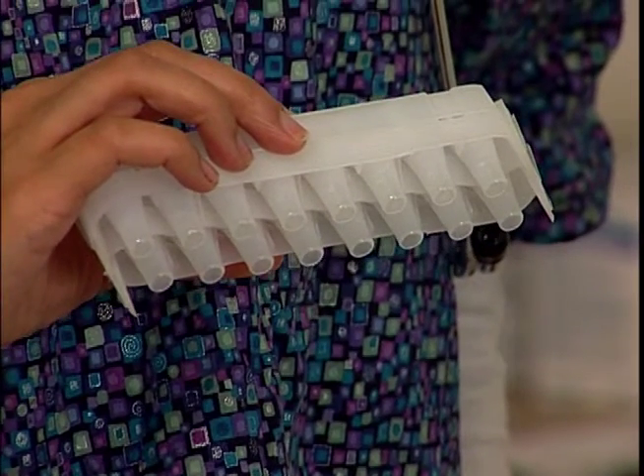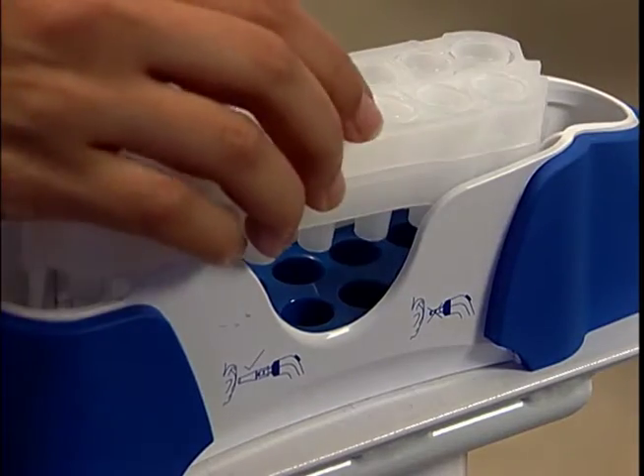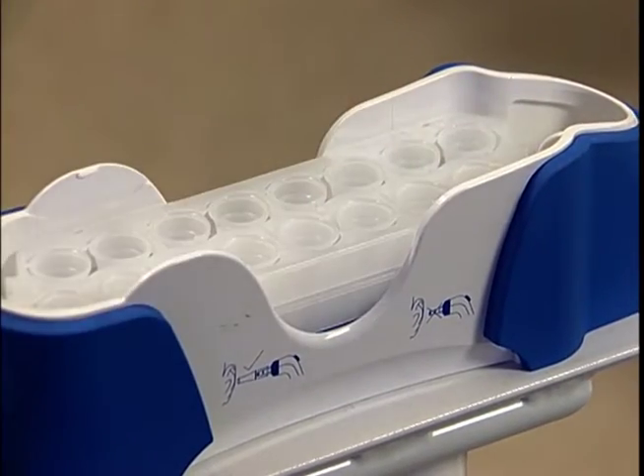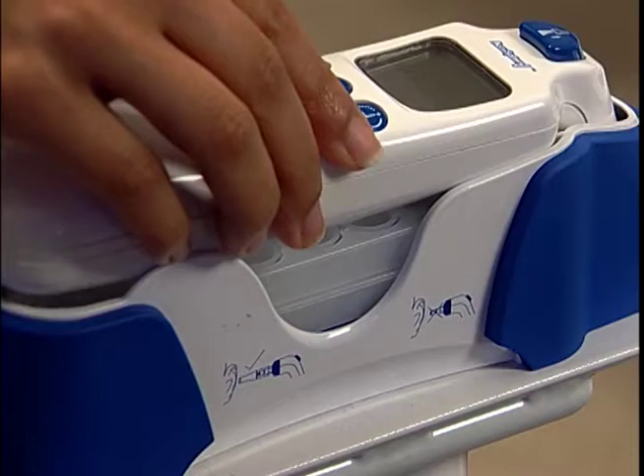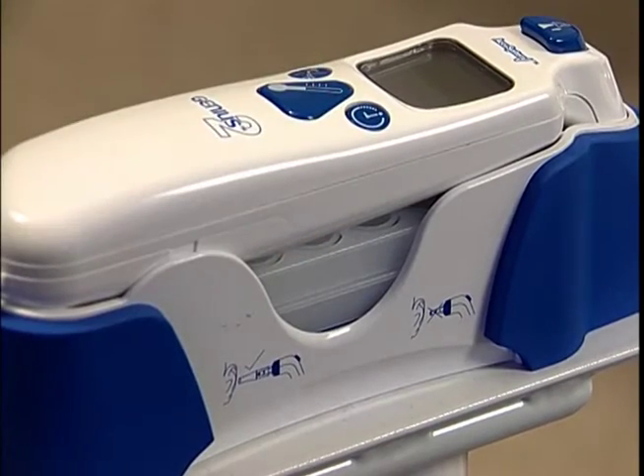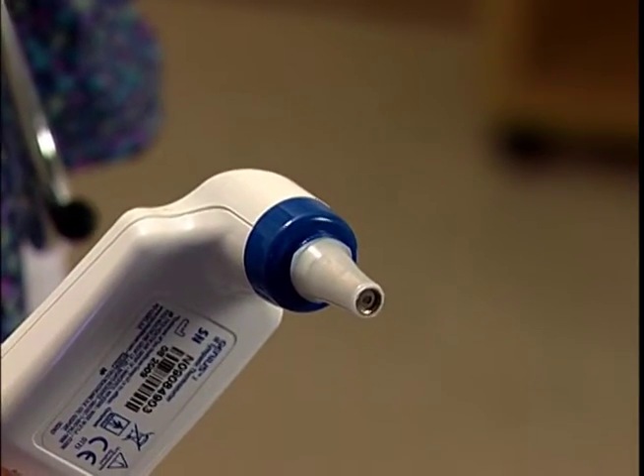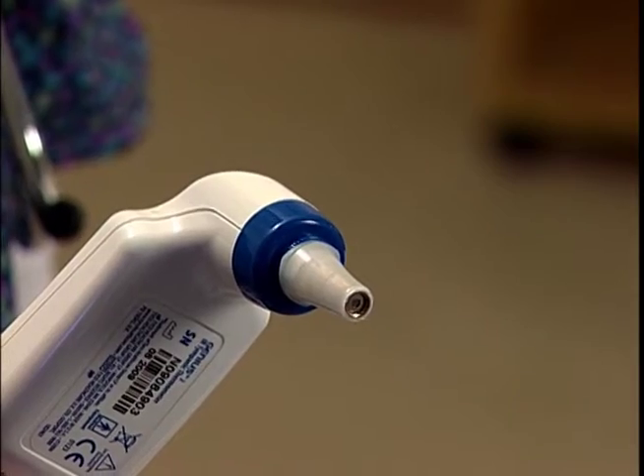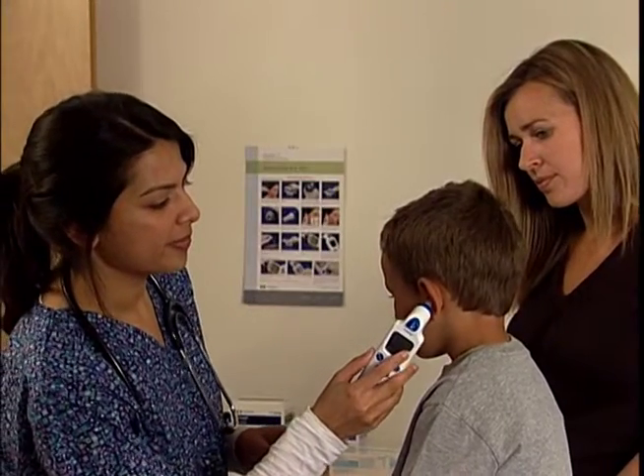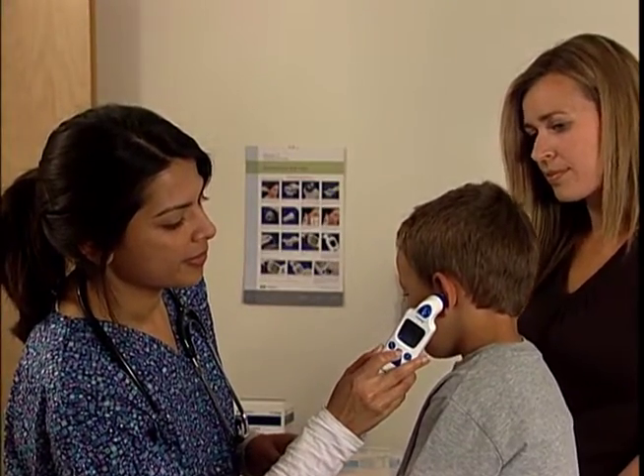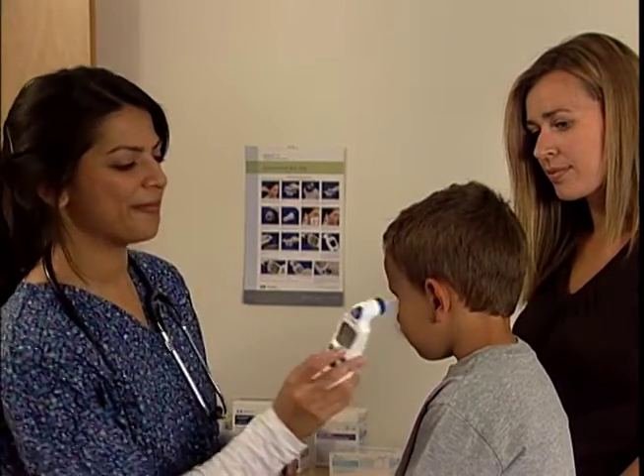To begin operation, install 2 cassettes of 16 probe covers and slide them smoothly into the base unit without touching or tearing the protective film on the tip of the probe cover. The Genius 2 will only operate when a new probe cover is installed for each use. The use of a new probe cover for each reading will guard against the possibility of cross-contamination and inaccurate temperatures.